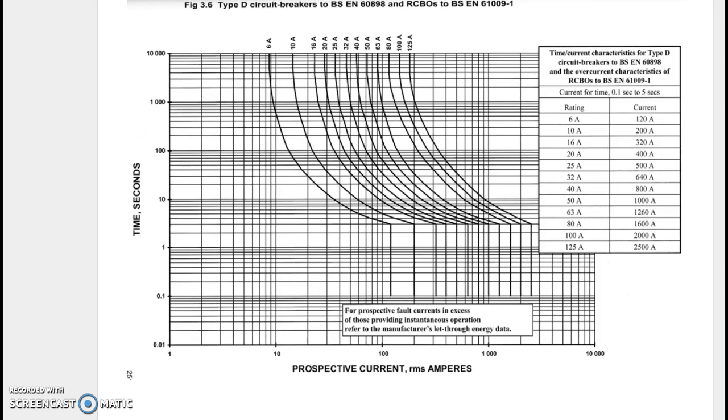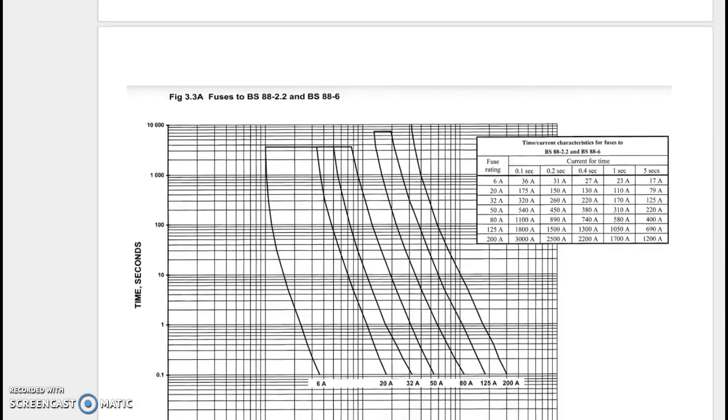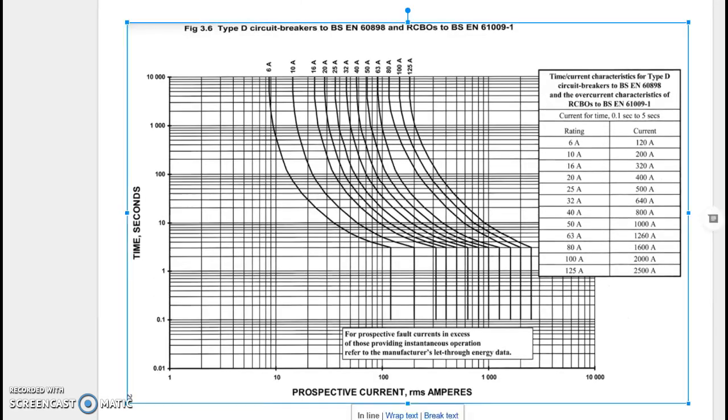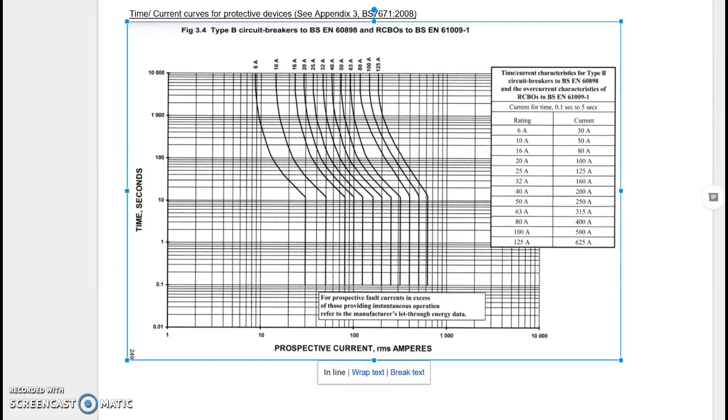Here we have the circuit breakers. You can see the big curves. That's the type D, so the type D at 6 amps needs 120 amps, that's a huge amount. Be careful those of you who change for nuisance tripping from a C type to a D type, make sure that your impedance is low enough. On a C type circuit breaker, a 6 amp device needs a current of 60 amps, it's coming down.